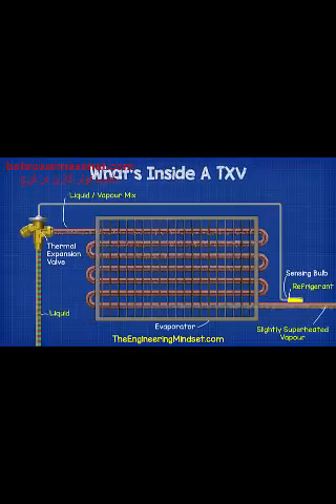The bulb is filled with a refrigerant which is kept completely separate to the refrigerant in the rest of the system. These two refrigerants never meet or mix, they are always separated. The superheat boils the refrigerant inside the bulb, and as it boils it creates pressure. The pressure travels along the hollow capillary tube and into the power head. The power head controls the flow of refrigerant, and we'll see inside that later in this video.